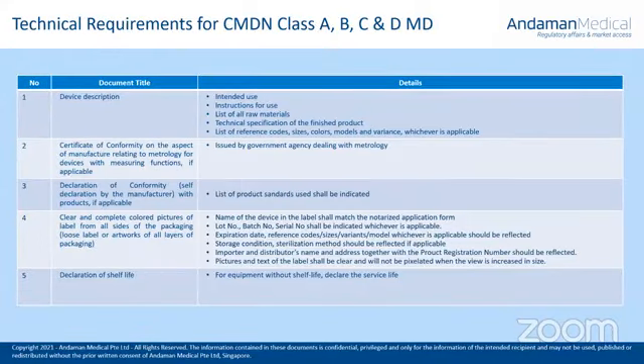We now go to the technical requirements of CMDN for Class A medical devices and Class B, C, and D medical devices not listed in Annex A. The reason why I mentioned Class B, C, and D medical devices not listed in Annex A is that currently we are still in the transition period, and those devices shall undergo the CMDN route. So the requirements are lesser than the CMDR, and these are the following.